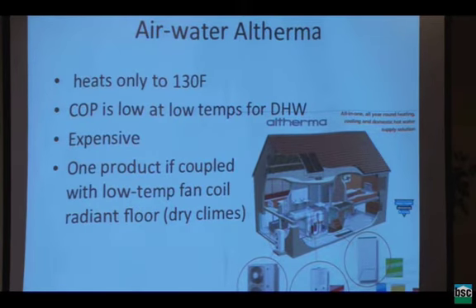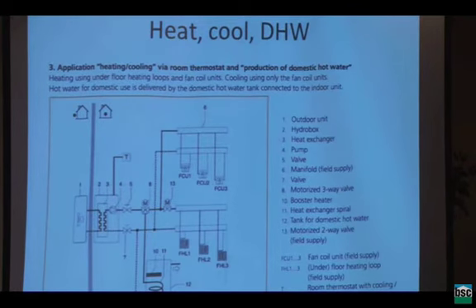But the advantage is this. You have one product that produces hot water for space heating. The same product produces domestic hot water, and the same product can be used for cooling in the summertime. So here's a chart of one of the installation methods for the Daikin Altherma. I have an outdoor unit, the refrigerant comes indoors, and therefore there it changes its heat into water. So you don't have any freeze problems. Okay, so that's smart. Now, that water could actually be used to heat the house or heat domestic hot water. And if you want to have an air conditioning mode, it can actually suck the heat out of a water tank that makes cold water for fan coils or floors, and take that heat and put it into domestic hot water. That should excite you.